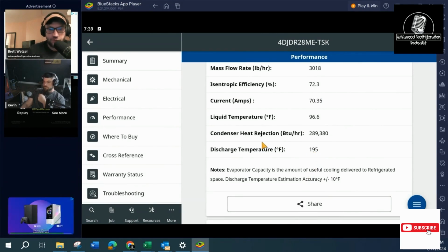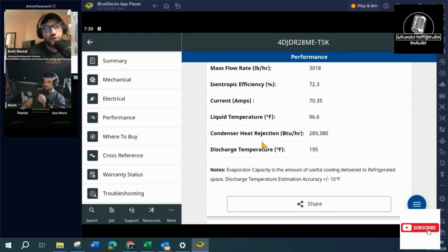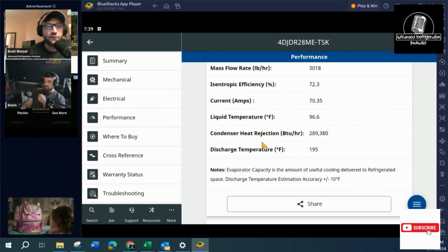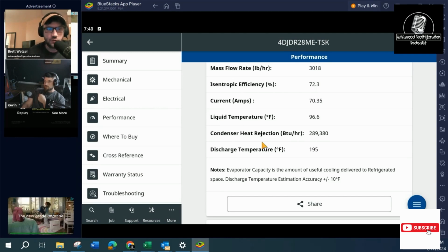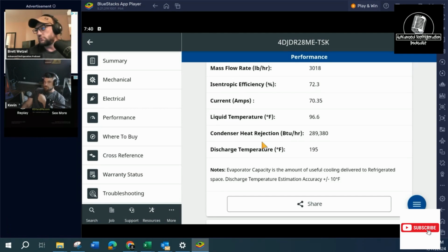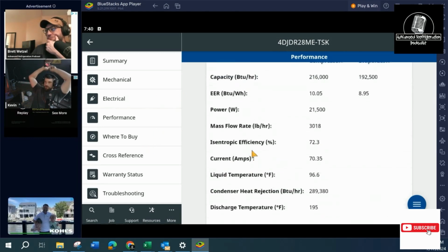So if you put all these numbers in there and lo and behold, this is exactly what you had, but your discharge temperature is running 240 degrees or 230, there's something probably mechanically wrong with that compressor. Correct. Now, Brett, run it with a plus 25.